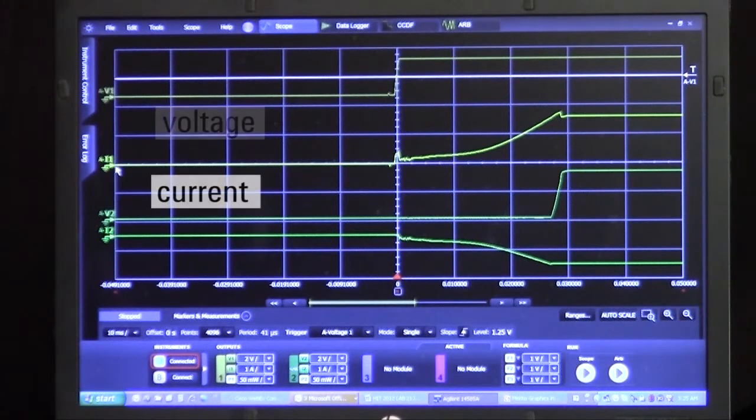The second trace here is the current being pulled out of channel one and you can see here at the time when the DC to DC converter power is applied, the current begins ramping up until the output is turned on. Now this is a unique capability of the DC power analyzer, the fact that it can measure current directly via a scope trace.